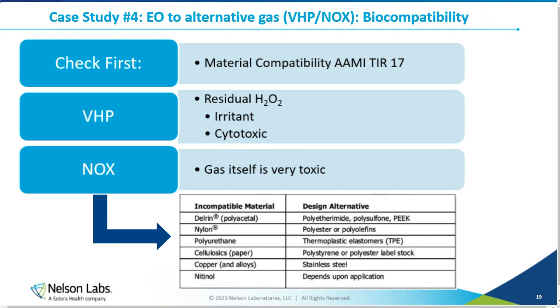For biocompatibility for VHP and Noxalizer, what we're really looking at, especially for VHP, is any residual hydrogen peroxide that remains. I know the residual for the sterilization cycle is stated to be water, which is true. But what we see is that there are still some residuals of hydrogen peroxide that are high enough to actually cause a positive response in either the cytotoxicity test or the irritation test. So these are tests we run for biocompatibility.